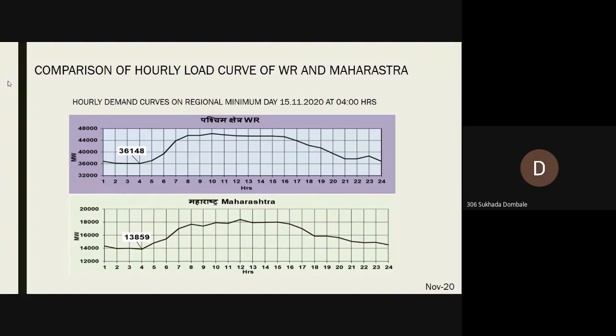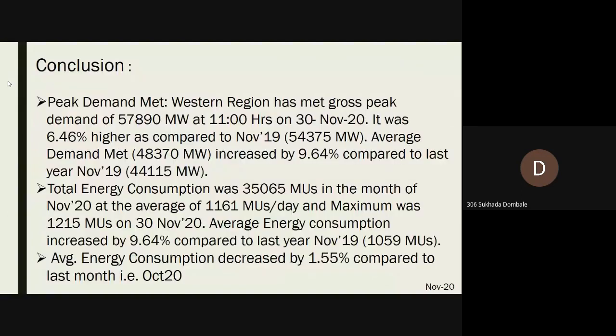The graph showing minimum demand for Western region and Maharashtra, that was 36,148 and 13,859 respectively on 15 November 20. So from all this data, we can conclude that in November 20, peak demand met, Western region has met gross peak demand of 57,890 megawatt at 11 hours on 30th November 20.